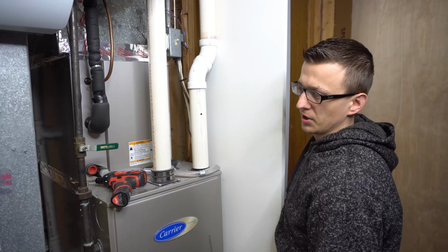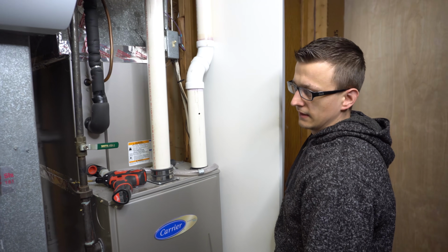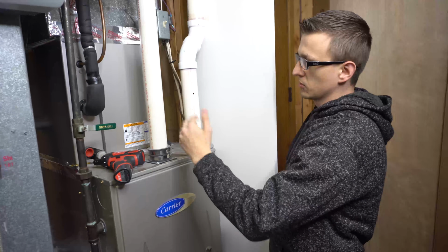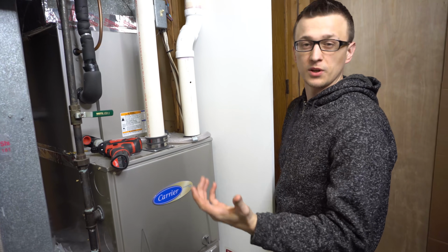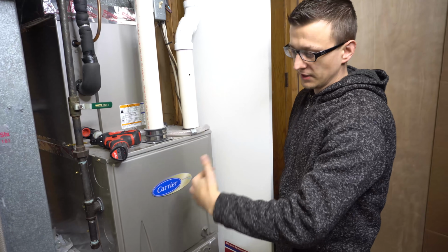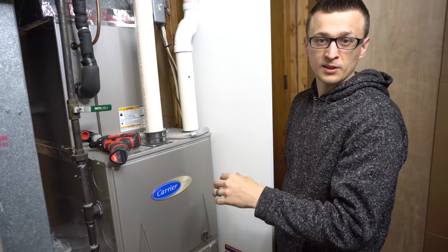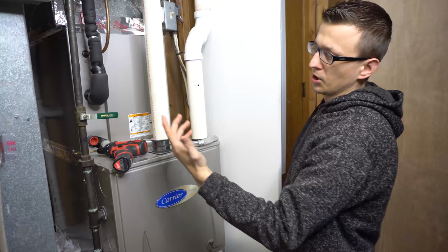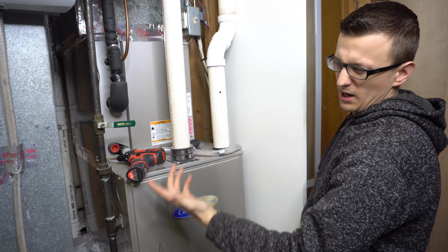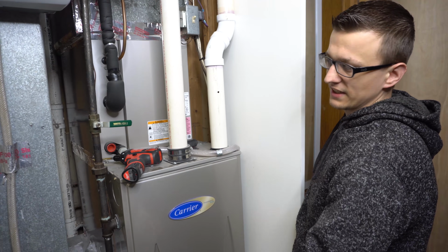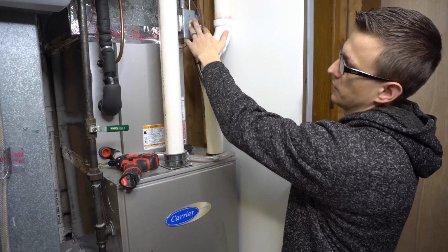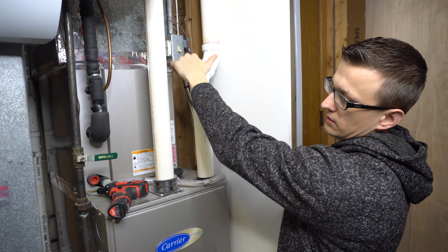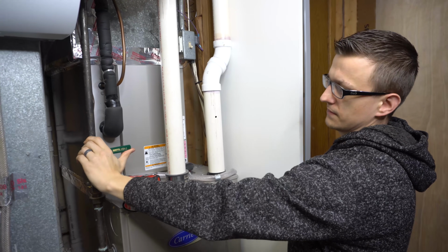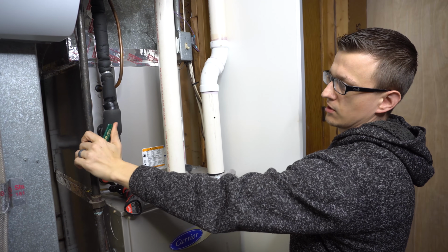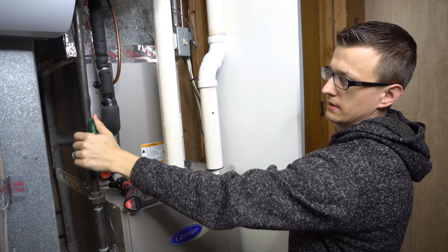That's if you're not just going to turn it off at the thermostat. So typically, after I check my carbon monoxide and all of that, if I'm doing a furnace inspection, I turn the power off and take the furnace apart and start looking at components inside. To turn it off, I turn the gas off, leave it off for about 15 or 20 seconds, and let it cool off a little bit before I hit the power switch. Turn it off, and I can turn the gas back on so I don't forget about it.